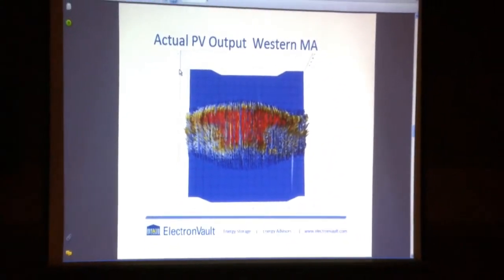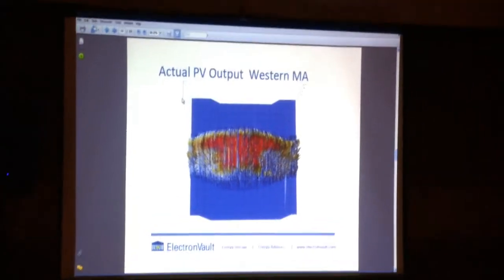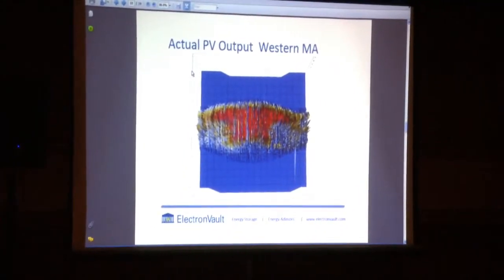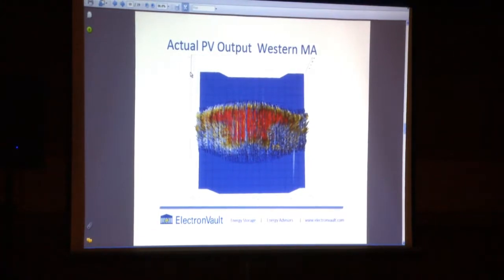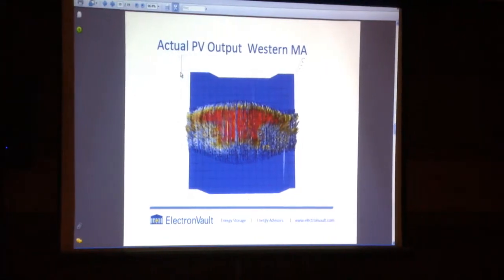You know, in California, we've got a lot of desert. We've got a lot of very sunny places. It's unusual. Much of the world is, shall we say, much cloudier. As they say in Boston, if you don't like the weather, wait 5 minutes. Yet there are megawatt photovoltaic installations all over the eastern seaboard. In many cases, they cause grid problems. One of the reasons for that is they can bounce up and down very, very quickly. And while you can control the rate with which a solar farm output rises just by controlling the controllers, the inverters, you cannot control how quickly it drops in its output unless you have storage.